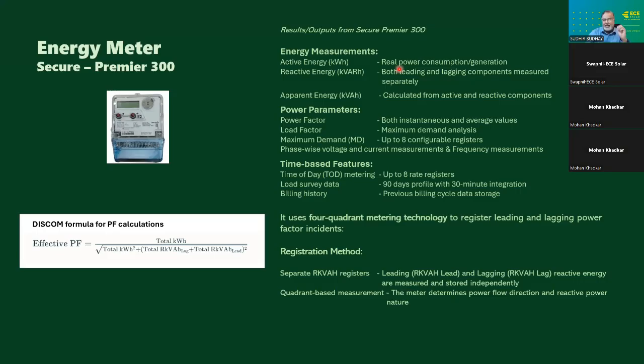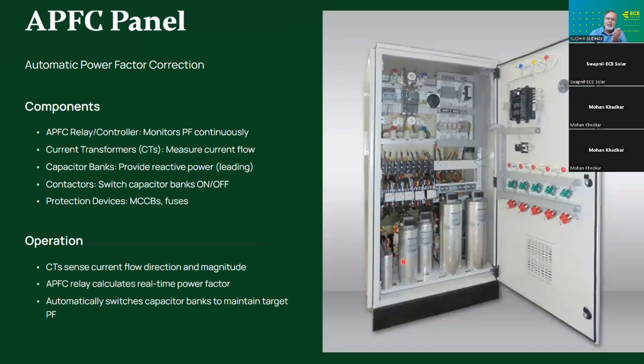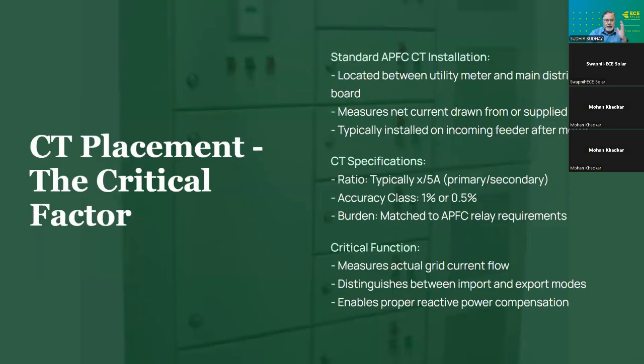Now, our target as an energy manager is to see that the bill is minimum for our customer. So our target is to see that the reactive power consumption is minimum, and how do we achieve it? Obviously by putting capacitors. These are mostly three-phase capacitors of various sizes depending on various loads. You keep on switching them using an APFC panel, and all of you are aware of it. So let's jump to the placement of CTs.